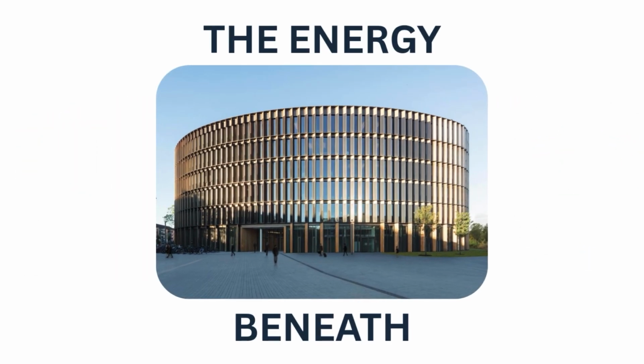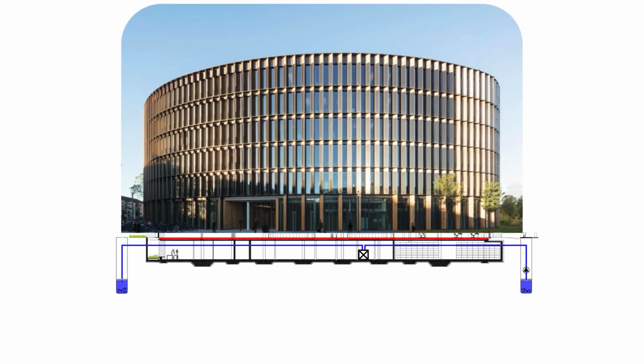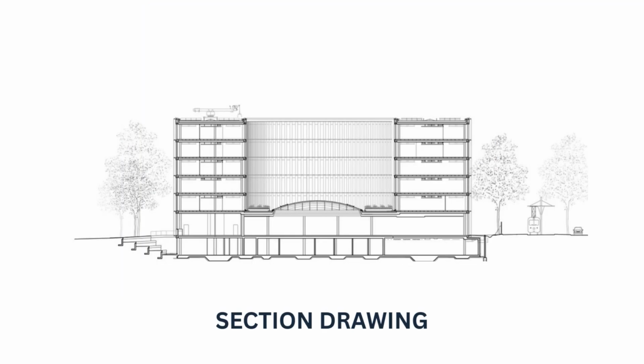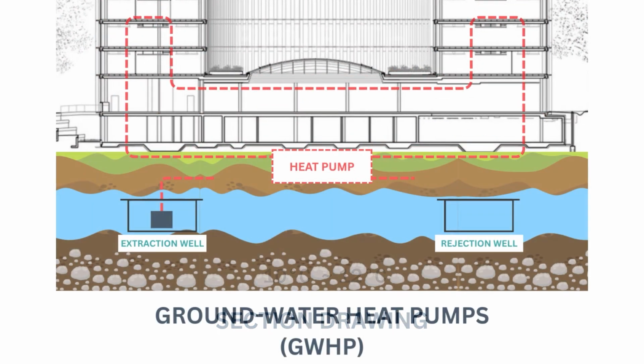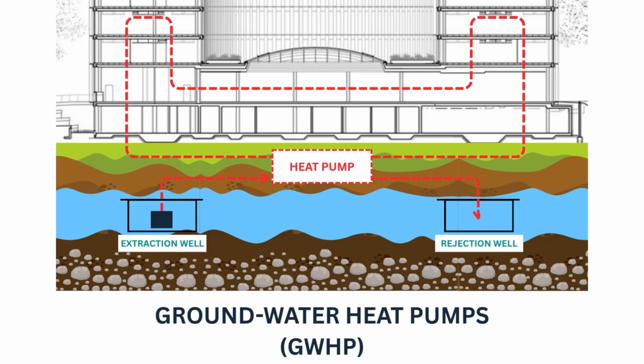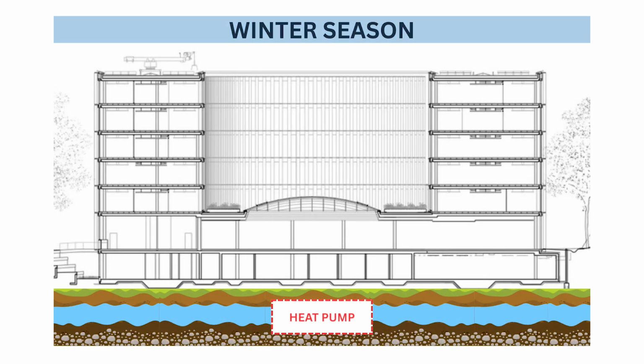Now, let's move underground. Below the town hall, a system of wells and pipes connects the building to the natural thermal energy of the earth. Just a few meters down, the ground maintains a steady temperature, roughly 10 to 12 degrees Celsius all year round. The system uses groundwater-coupled heat pumps, each acting as a thermal engine that moves heat between the earth and the building. Here's how it works.